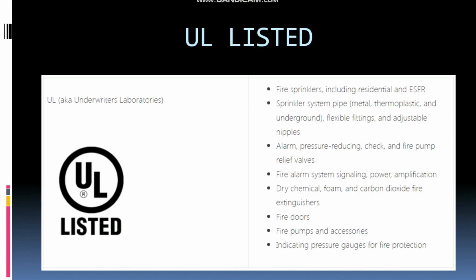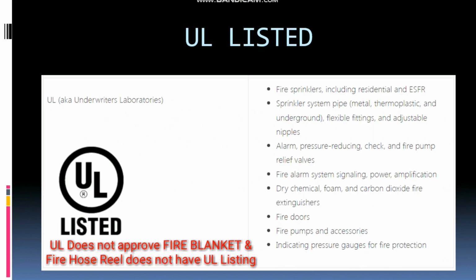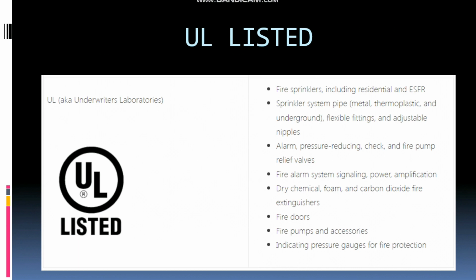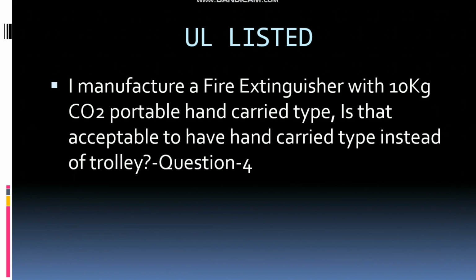And here I highlighted different types of UL listed items, like fire sprinklers, including residential and ESFR sprinkler system pipes, whether ferrous or non-ferrous, like metal pipe, thermoplastic like CPVC pipes, and underground pipes, fire alarm systems, fire doors, fire pumps, and indicating pressure gauges. So these are the items under UL listed.